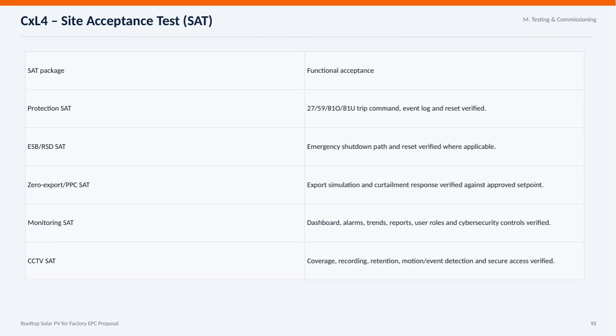On this slide, we focus on the Site Acceptance Test, or SAT, for the CXL4 project, specifically within the testing and commissioning phase of our rooftop solar PV factory proposal. The SAT package covers several critical functional acceptance tests to ensure everything works as intended. First, the protection SAT verifies the trip commands for various protective relays, event logs, and reset functions. Then, the emergency shutdown, or ESB/RSD SAT, checks the emergency shutdown path and reset mechanisms where applicable. The Zero Export and PPC SAT involves simulating export conditions and verifying curtailment responses against the approved set points.